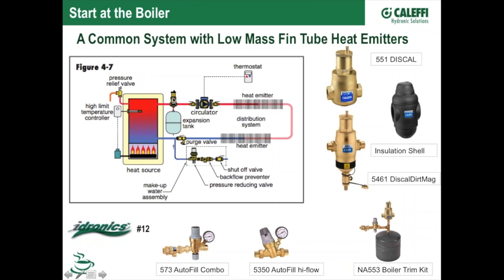And right here you'll see an air separator, an expansion tank, fill valve, purge valve on the back side of it. What happens on a system is we heat water, the first time we put the water in there, there's some air in there, there's some dissolved air in there, there's some big bubbles. We'll purge those out, and then we want a device that'll keep working after we leave, and it'll grab little bubbles that we can't get out on the initial purge for whatever reason. And that's why we want to have this device right at the boiler. At the hottest point in the system and also at the lowest pressure point is the best place to get air out of a system.